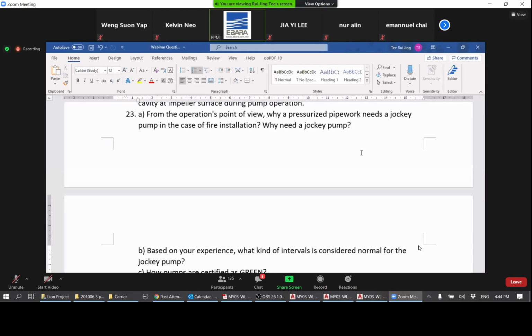Now, in such a system, there are always some small leakages that could reduce the pressure inside the pipeline. Because your fire system or pressurized pipework is activated by pressure switches at the pump site, what you don't want is a big main pump starting to run because of a small leak, and pressurizing the pipework. If this leak is constant, your main pump will keep turning on and off just to pressurize. So a jockey pump, which is a much smaller pump, usually sized at 5% of the total flow rate, is used for this purpose. Whenever there is a leak and the pressure starts to drop, only the jockey pump will run to pressurize the pipework. So that's the main function.